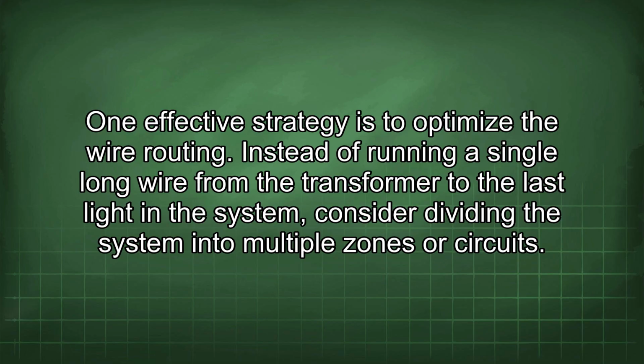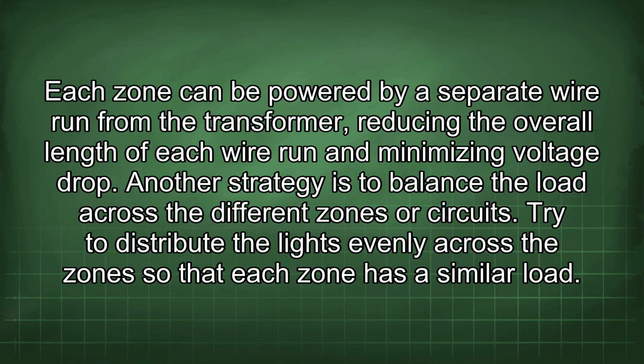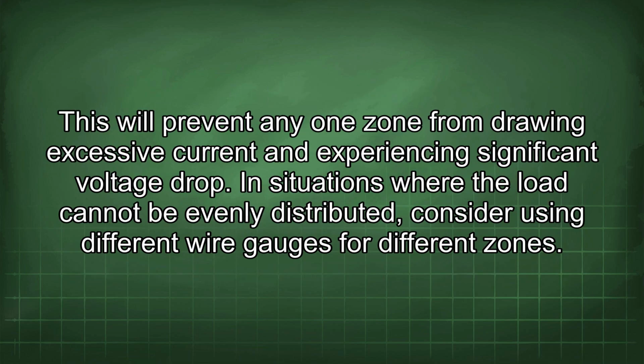Instead of running a single long wire from the transformer to the last light in the system, consider dividing the system into multiple zones or circuits. Each zone can be powered by a separate wire run from the transformer, reducing the overall length of each wire run and minimizing voltage drop. Another strategy is to balance the load across the different zones or circuits. Try to distribute the lights evenly across the zones so that each zone has a similar load. This will prevent any one zone from drawing excessive current and experiencing significant voltage drop.